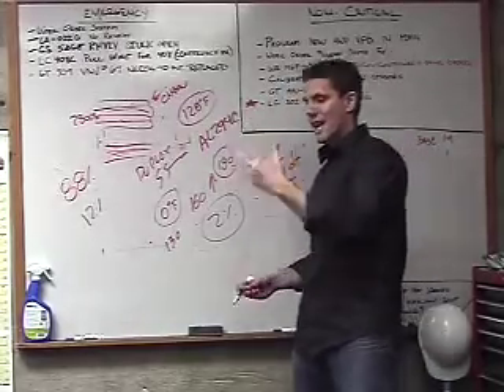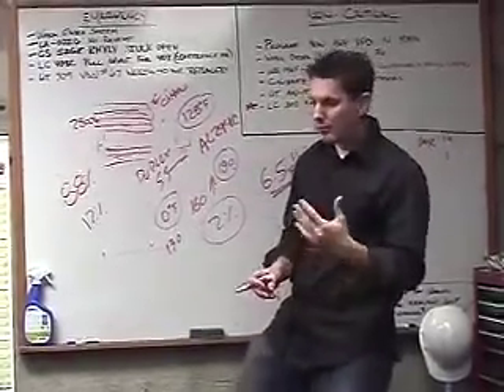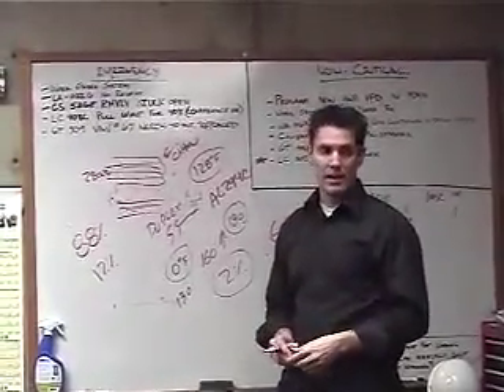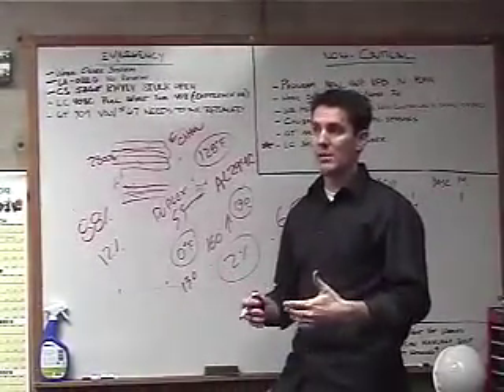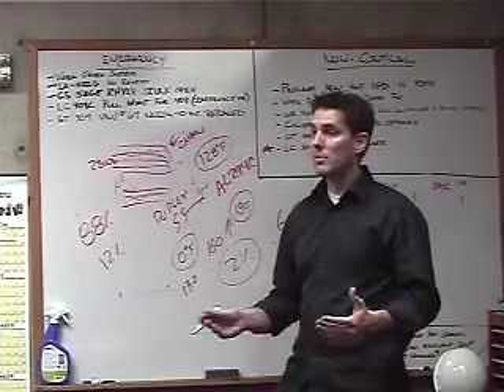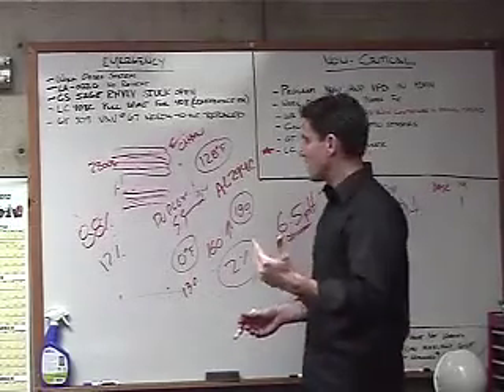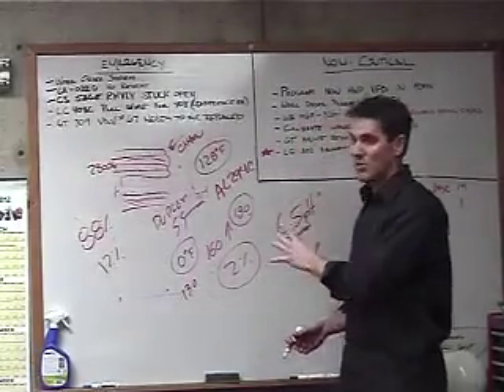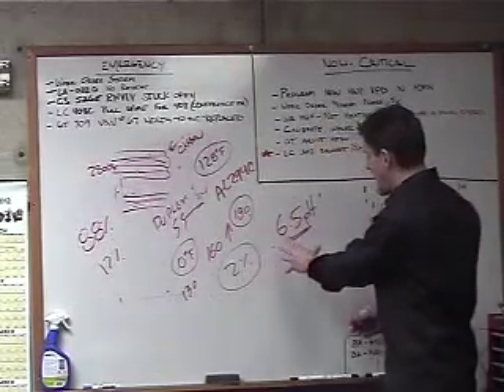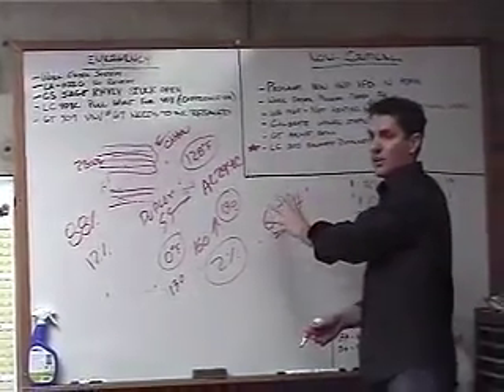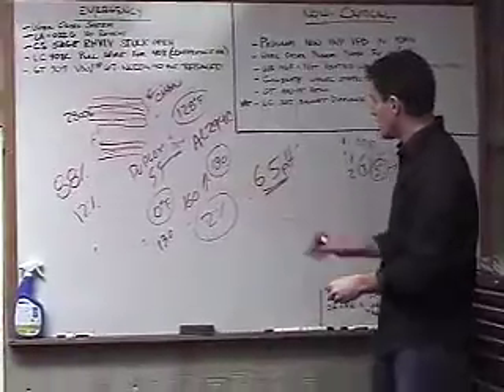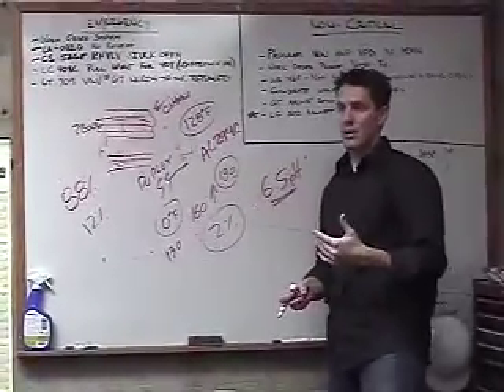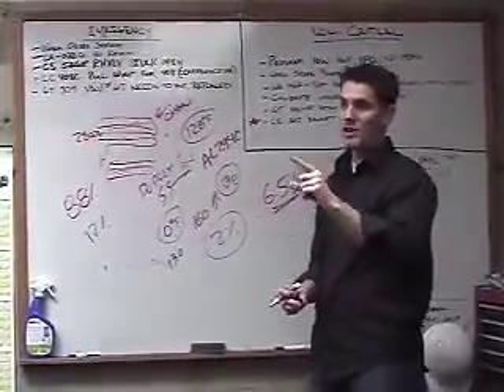Condensing boilers came out predominantly around the late 80s, early 90s. So we're now getting to a point where we're starting to see buildings fail. Who's going to pay for this? So we as manufacturers, we recommend, hey, this should be neutralized somehow. We've got to get it back up to a neutral level so that it's not going to eat through this material. So somehow we've got to do that. The easiest way is to run it across lime deposit. And that's what we've given you on your boiler.